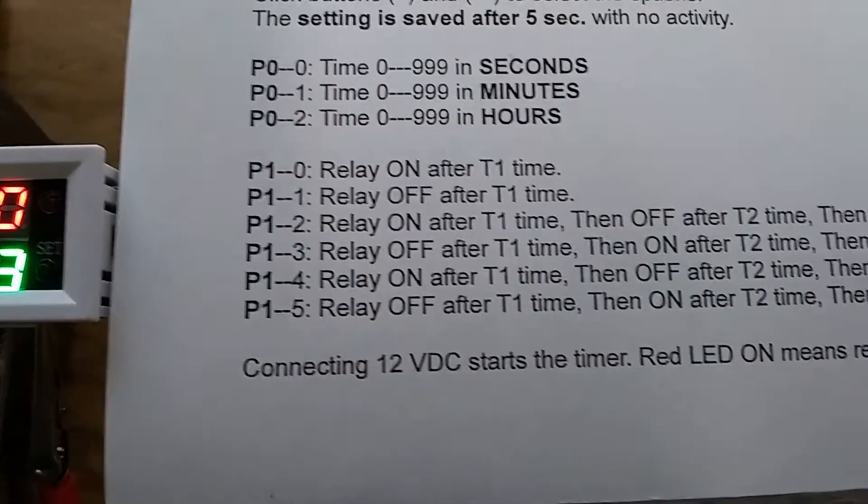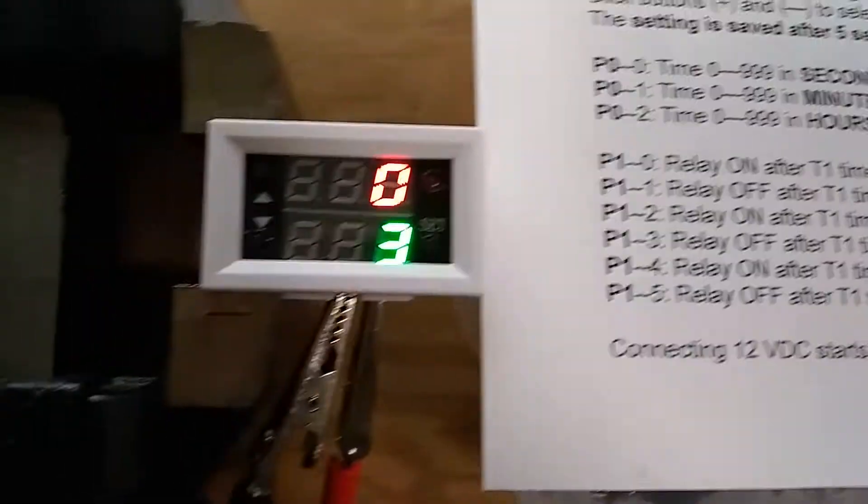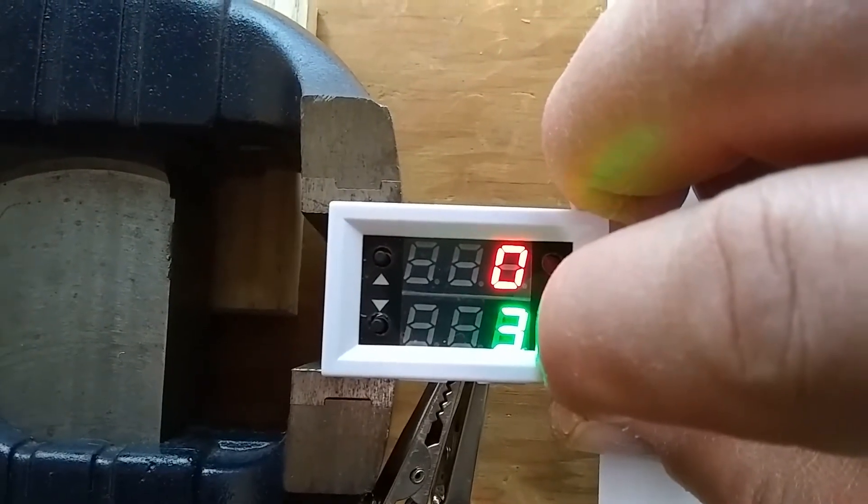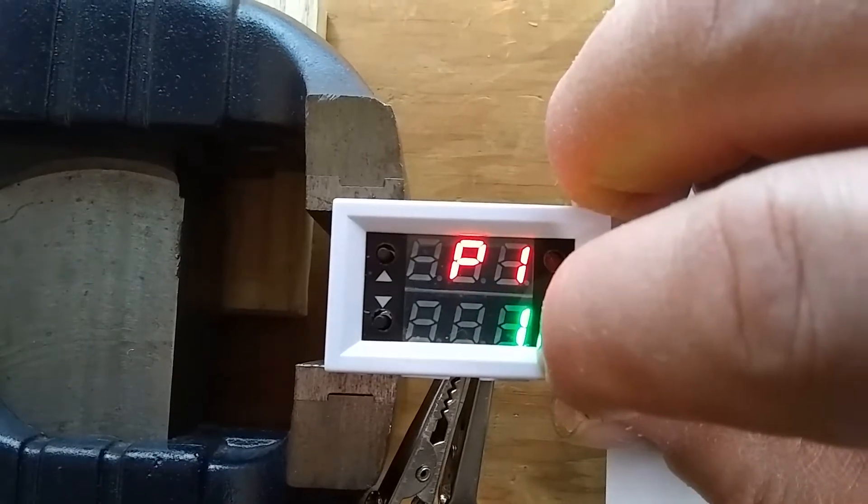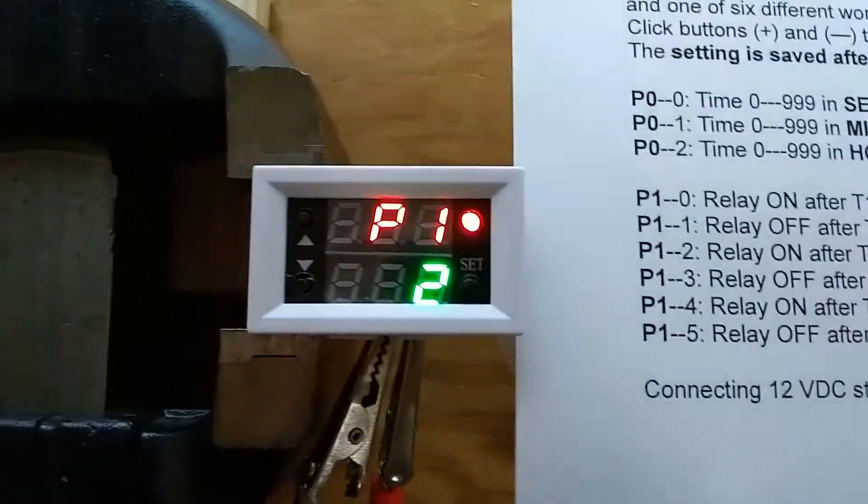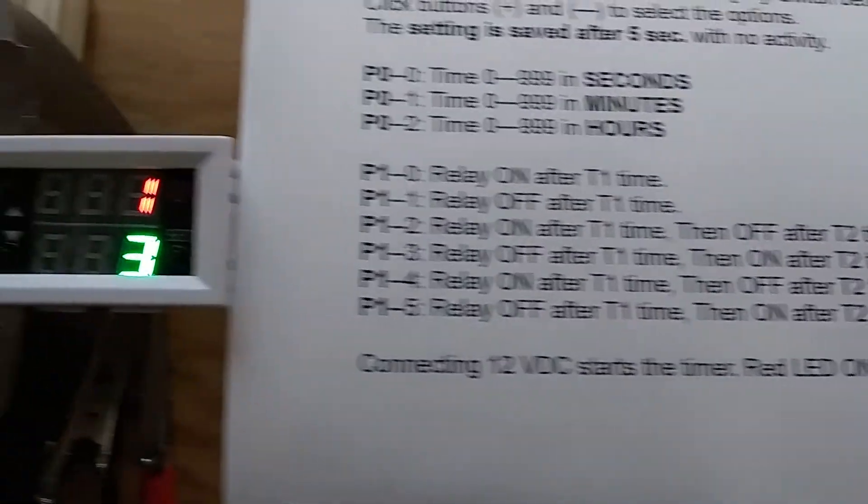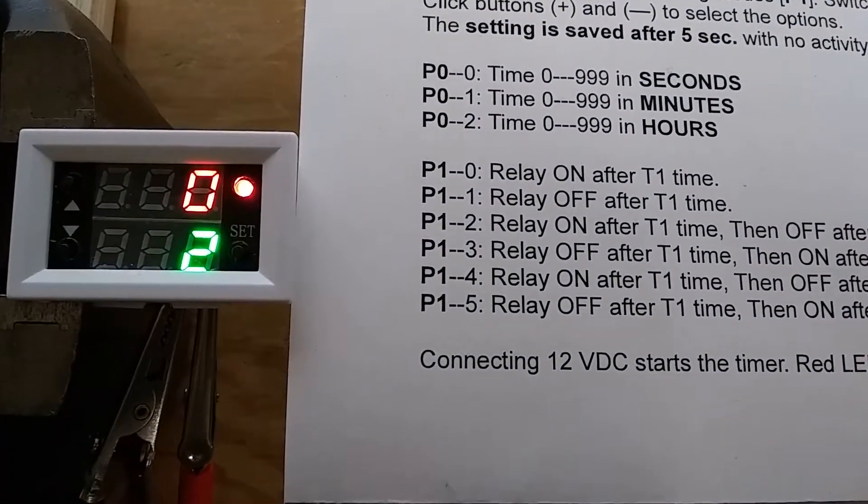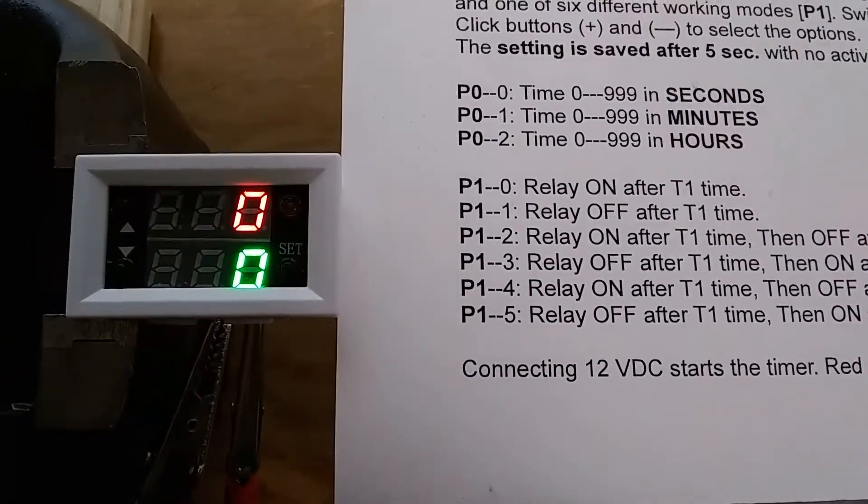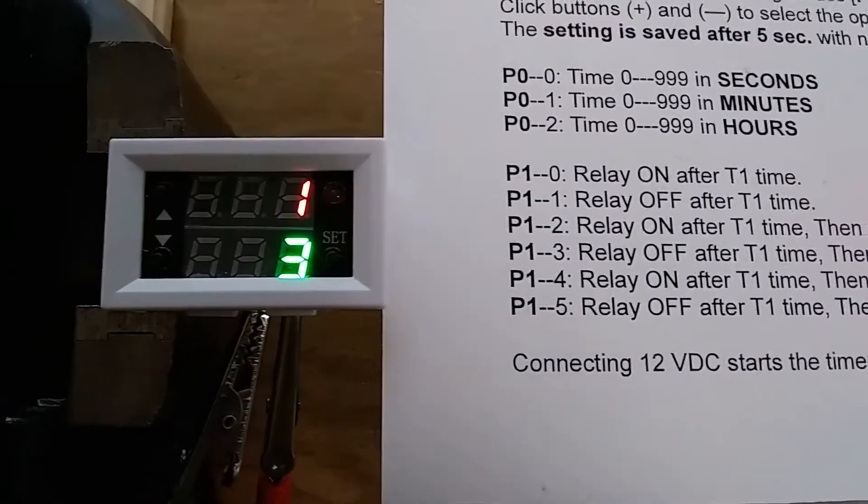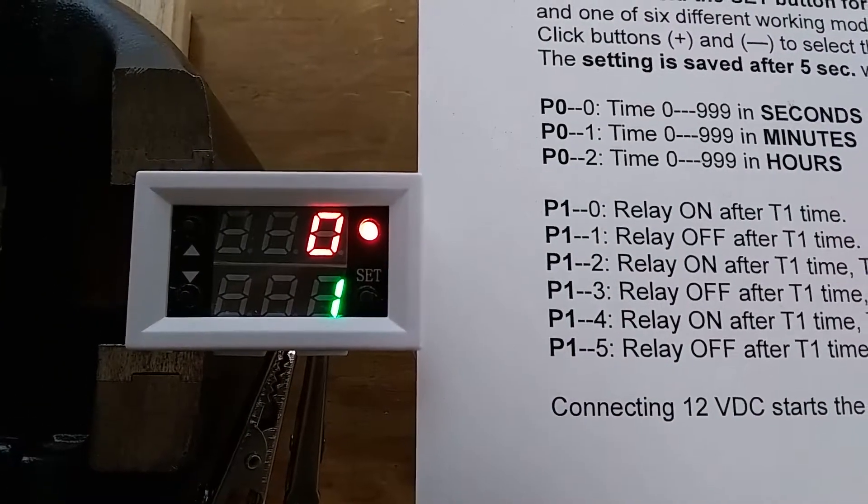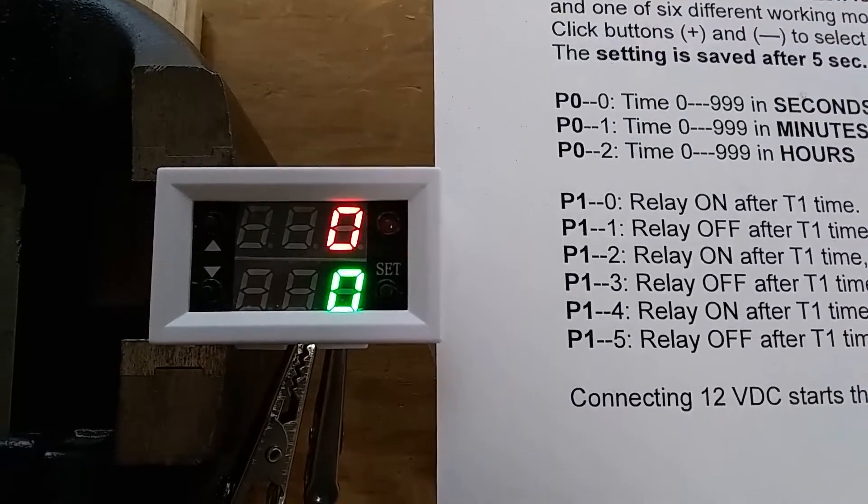Now, let's go to the next option. Relay on after T1, off after T2. I hit it again for five seconds. Now we have P1-2, and P1-2 will be relay on and then off. Let's just disconnect the power and try it again. We have three seconds on after two seconds delay.